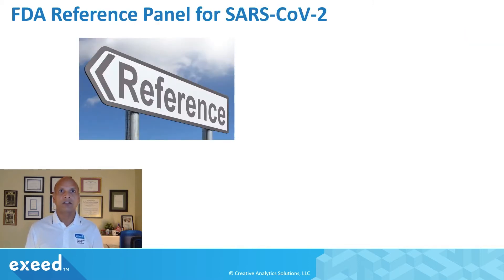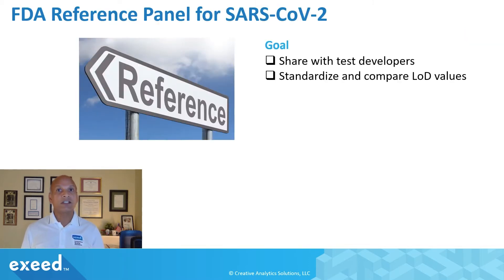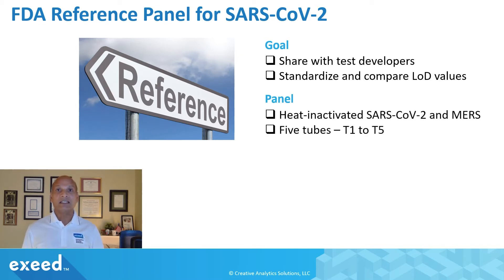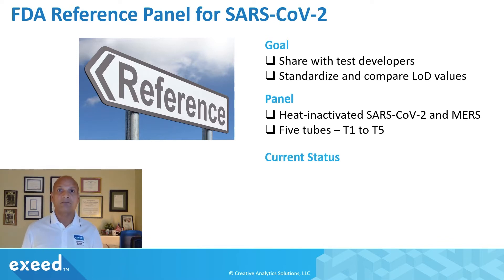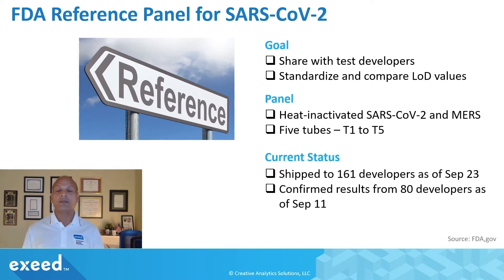It is not possible to compare LOD of different tests unless a reference panel and standard protocol is used, and that's what has happened now. The FDA reference panel goal is to share with test developers a standardized way to compare LOD values. The panel is a heat-inactivated SARS-CoV-2 strain and MERS-CoV strain, provided in five tubes T1 through T5. Only the concentration in T1 is known. The FDA has shipped this panel to 161 developers as of September 23rd, and confirmed results from 80 developers as of September 11th, published on FDA's website.